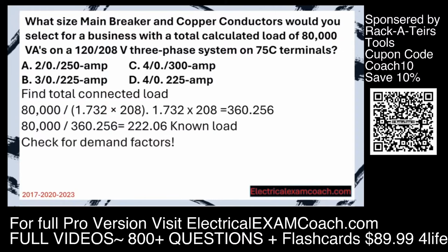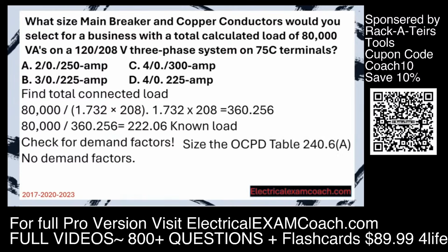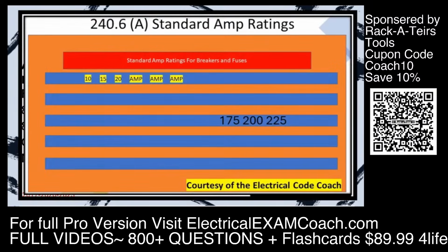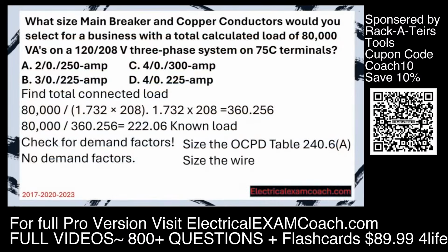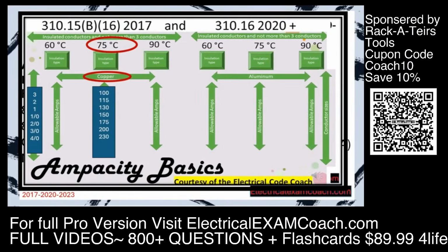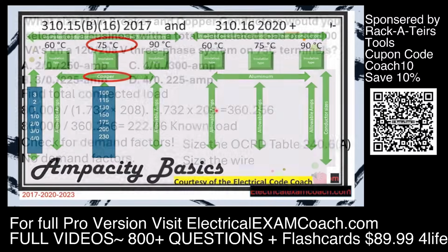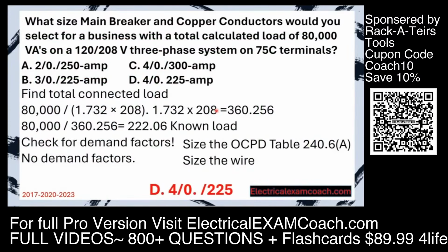But first, we must check for demand factors. In this case, there are no demand factors, so we can size like normal. Let's size our overcurrent protective device first, based off of 222 amps. We head to table 240.6(A) and we choose the next standard size, and in this case, it's going to be a 225. Now we can size our wire. We head to our primary ampacity table. We're going to be on the copper side of the table in the 75 degree C column, and we need to go down and find a wire that covers 222 amps. In this case, we're going to select a 4/0. When we put it on a 4/0 wire, we're going to select D, and we're all done.